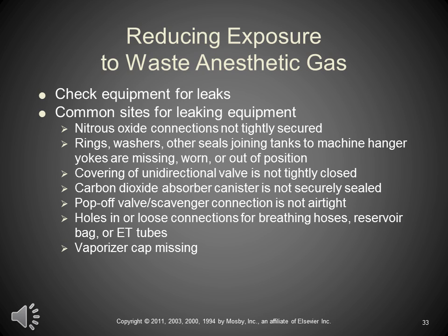And the vaporizer cap is missing, and I've seen people do that. Take the cap off the vaporizer, fill it up with isoflurane, forget to put the cap back on, just not seal it back up. And about the first time you hit that O2 flush, you're going to have anesthesia flying all over the room. It looks like a fountain.